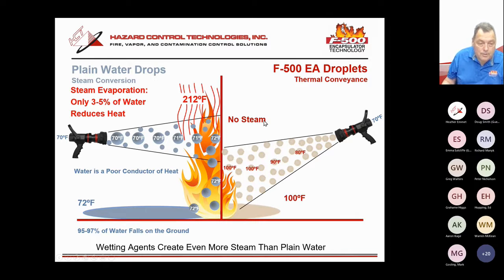With the F500, we're coming out at 70, but we're transferring the heat to the internal portion of the droplet - 80 degrees, 90, 100, 110. Since water steams at 212 Fahrenheit, and we're only at 100 to 110 Fahrenheit, we do not create any steam. We're absorbing the heat into the internal portion of the droplet.